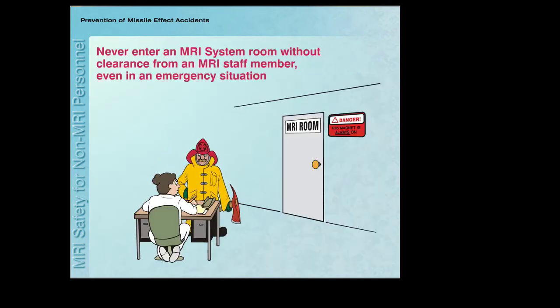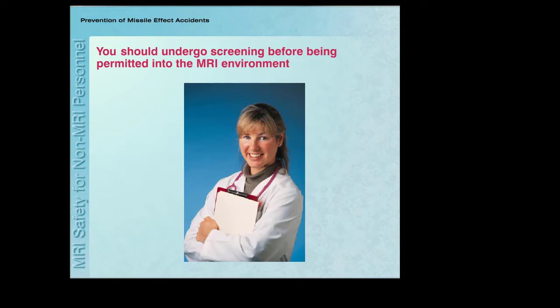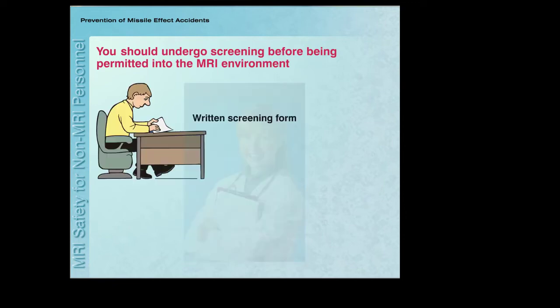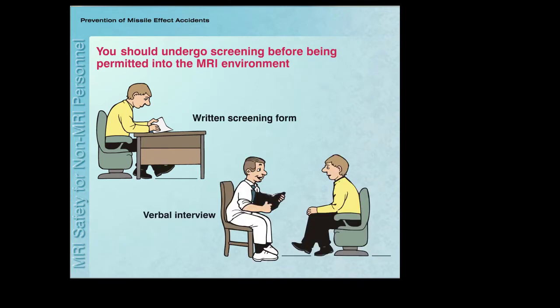You should never enter the scanner room without clearance from an MRI staff member, even in the event of an emergency. MRI safety-trained personnel are responsible for performing screening of all individuals before allowing them to enter the MRI system room. Therefore, you are required to undergo screening before being permitted into the MRI environment. Screening involves the use of a written form and verbal interview to identify items that might pose safety or other problems. Part of the screening procedure is to identify items that are not allowed into the MRI system room. These items include things such as external metallic objects and internal implants.